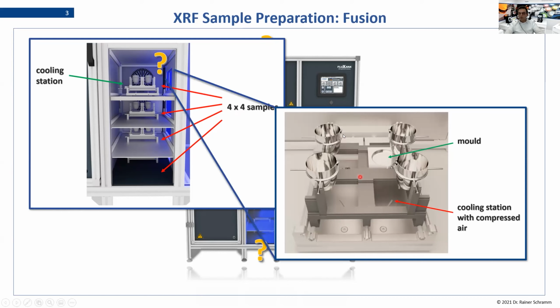And you see here how the crucibles are placed in the holder. They are side by side, and underneath the crucibles sits the mold, so that you have 4 molds and 4 crucibles in one holder. And on that cooling station, you can see that the cooling is done by compressed air, which is the best way we use to cool down beads, like we do it on all our other fusion systems.